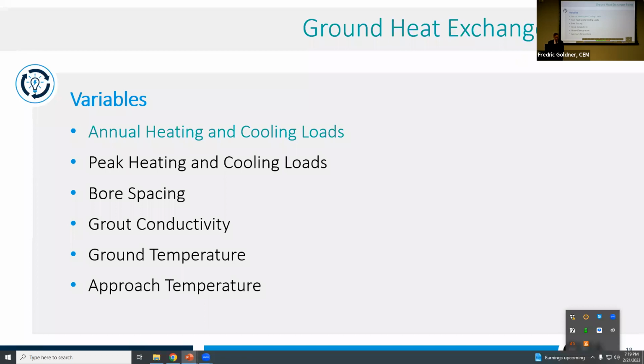A lot of people tend to get caught up in those peak heating loads and think that they need to, like what we used to do as engineers traditionally, design for the cooling design day or the heating design day. So now I've got this boiler that's rated for 400,000 BTUs, but I only need 400,000 BTUs 3 hours of the year out of 8,760. That's the kind of approach or the concept that I'm trying to explain. You don't need to invest in that peak. You can rely on everyone else's loads to help flatten and soften those peak demands.